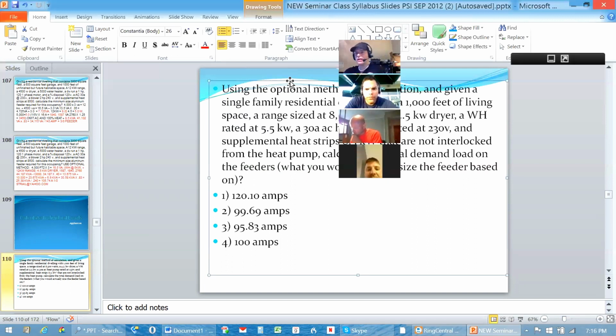So we're using AC instead of the heat strips, right? On this question, we'd use the AC instead of the heat strips because the AC is bigger. No, this is a heat pump. And the heat pump's going to be on in both conditions, whether it's the air conditioning or the heat. The heat pump works just in reverse operation, but it's still the same piece. So it's going to fall under Section 3.